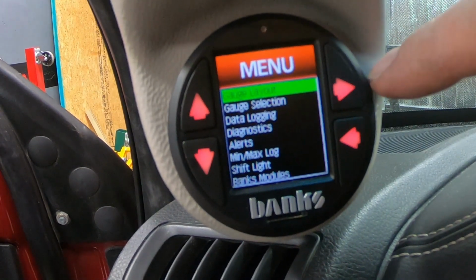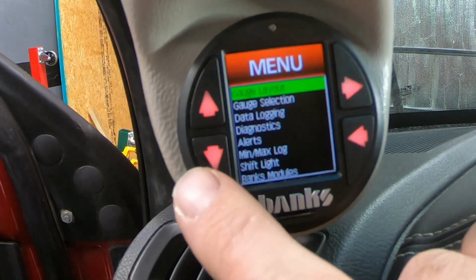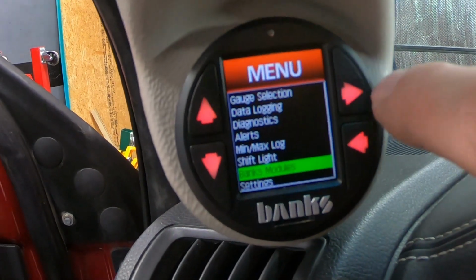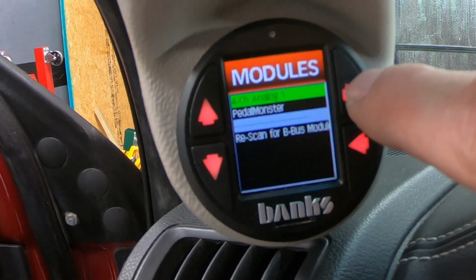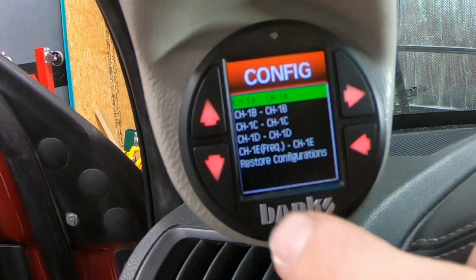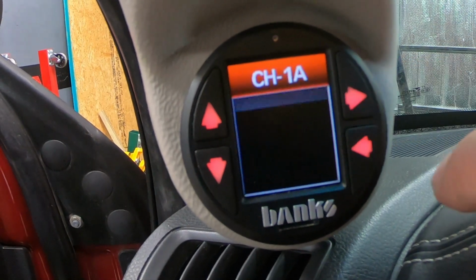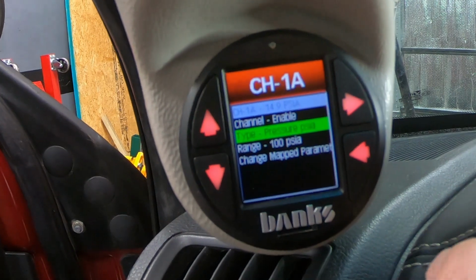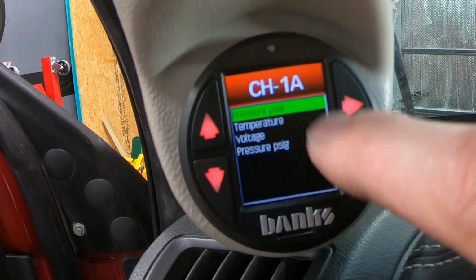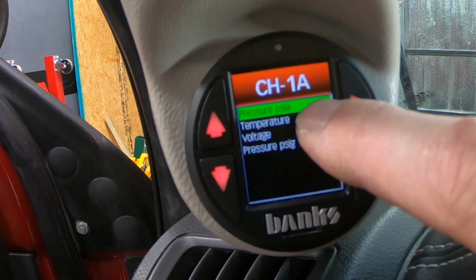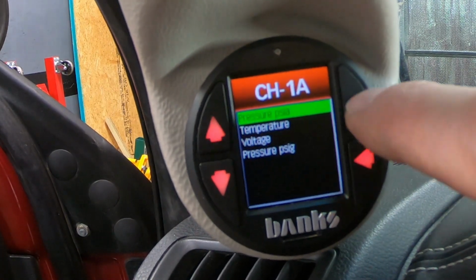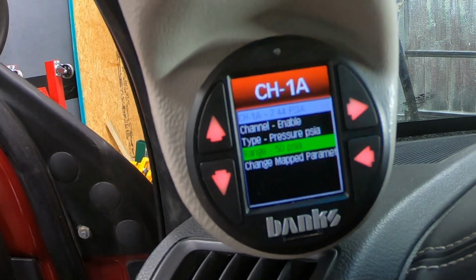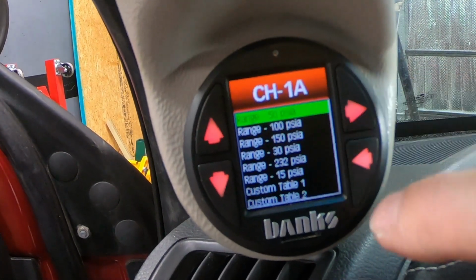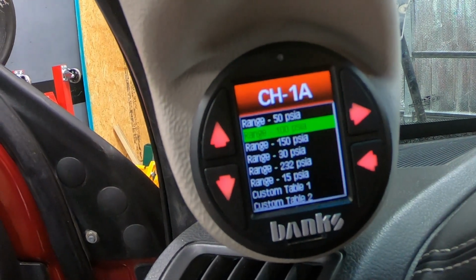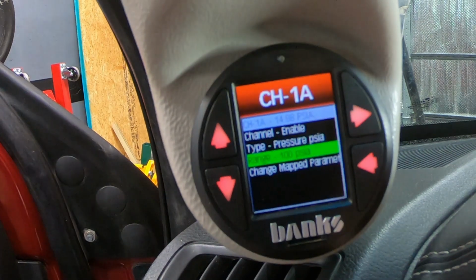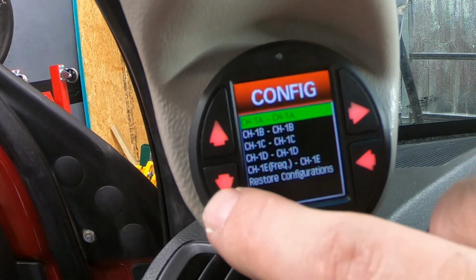If we hit the right arrow here and go back to our main menu, then down into Banks Modules, 4-channel analog, select the one we have. If we configure channel 1, you see it's enabled. It was set to voltage, but we're going to set it to pressure PSIA, because these are PSIA sensors. Channel A is our fuel sensor, so we change it to a range of 100 PSIA, then back up and do the same for channel B.